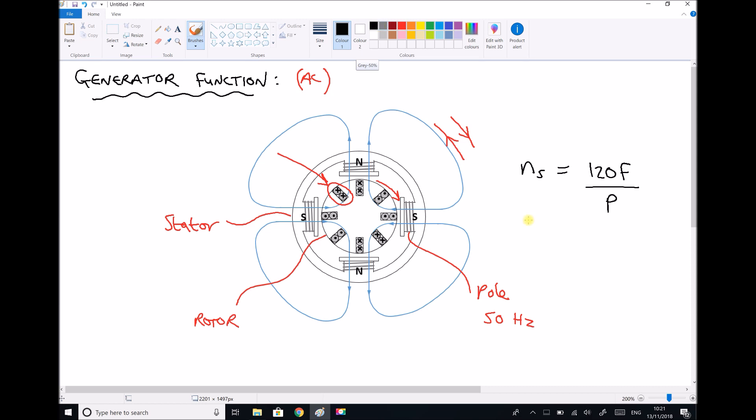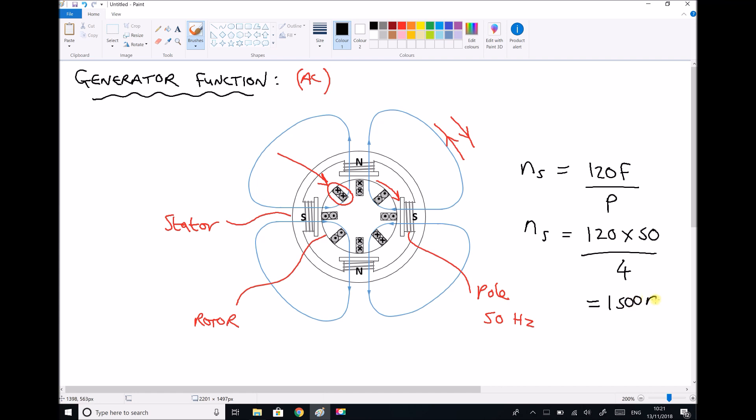We have NS, the synchronous speed, equals 120 times the frequency. We've already said the frequency of UK mains is 50 hertz, divided by the number of poles. The machine we're looking at here is a typical four pole machine. When we calculate that we get a synchronous speed of 1500 RPM.